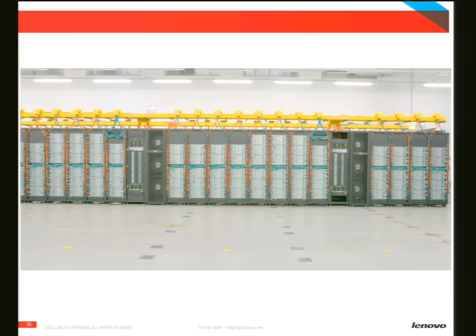It's doing the first acceptance test, it's doing the first Linpack test, of course, and it's really following the measurements that we did up front on the sample nodes, where we clearly can see that with the inlet temperature between 18 and 45 degrees C, we have very stable, very flat performance scores. That's also true for all the other applications, so that you really can operate your data center according to the outside air. And that's really what LRZ is doing.